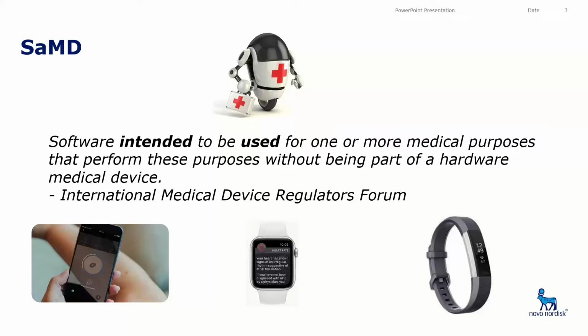So in this picture already, you can see that some software, so if we say that the intended use of the picture on the bottom left is actually to establish if the skin is or might be cancer, then that falls most probably under the software as a medical device category. Absolutely. Especially if it also gives a therapeutic suggestion. In the middle, we have an Apple Watch, which in version 4 has been cleared by the FDA for atrial fibrillation. So again, a medical device there, with software within it, and we'll talk about AI in a bit. And then we have a sport watch that, even though it gives us biometric parameters back, like heart rate and maybe stress, is not a software as a medical device. So the software running in these devices is not software as a medical device. Okay. And the product itself is not a medical device.